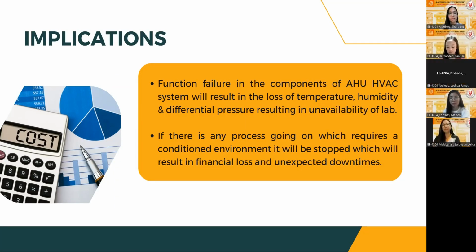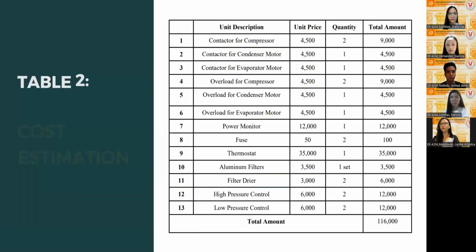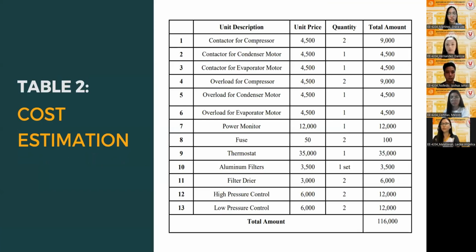Moving on to the implications, functional failure in the components of the AHU HVAC system will result in the loss of temperature, humidity, and differential pressure, resulting in unavailability of the lab. If there is any process going on which requires a conditioned environment, it will be stopped, which will result in financial loss and unexpected downtimes. Next. As per the original equipment manufacturer, the cost of common spare parts of an AHU-based HVAC system is shown in this table. As you can see, starting from the contactor for the compressor until the low pressure control, we have a total amount of 116,000 pesos. Next.